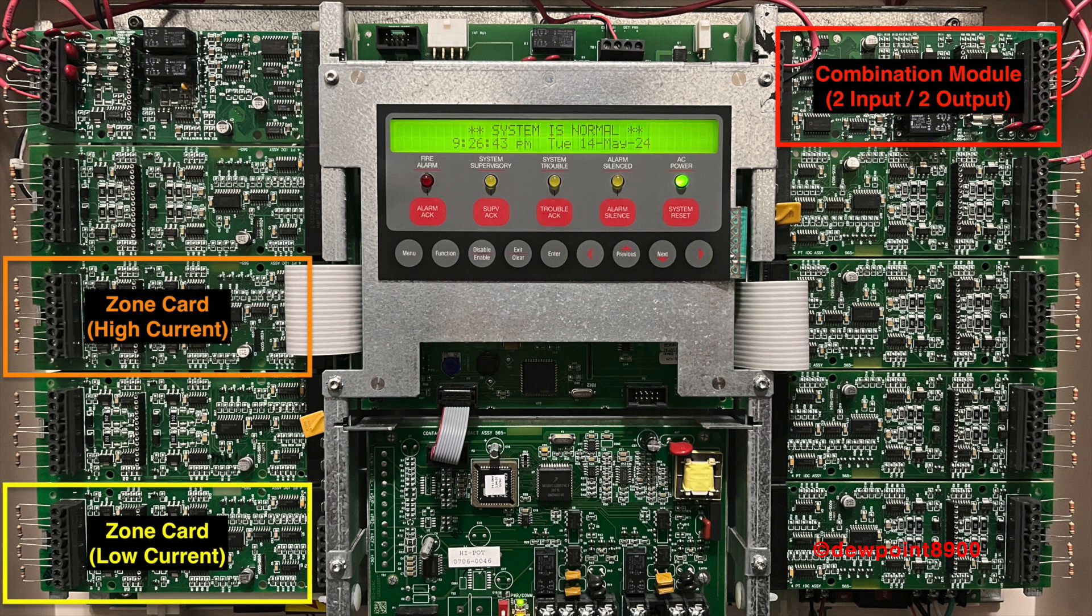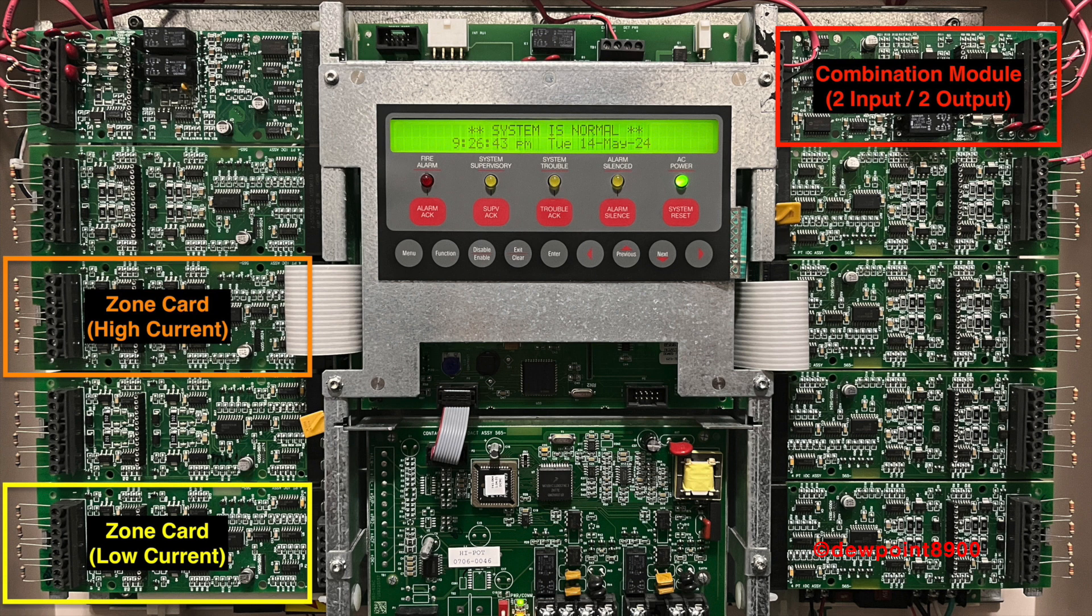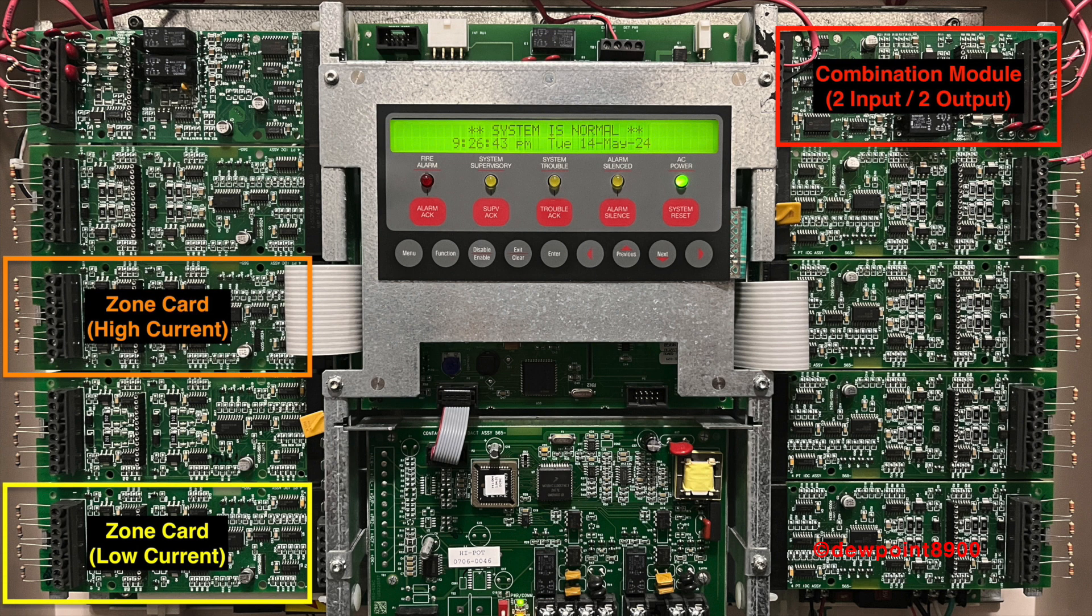This 4005 is filled to the maximum capacity of 10 cards. There are five types of cards that can be used on the 4005. These include two types of zone cards, low current and high current. Both cards provide four zones each. The low current zone card can handle up to 20 detectors per zone, while the high current card can hold up to 30. This high current zone card is also required for detectors with relay bases, and was included in the 4002-4005 retrofit kit.